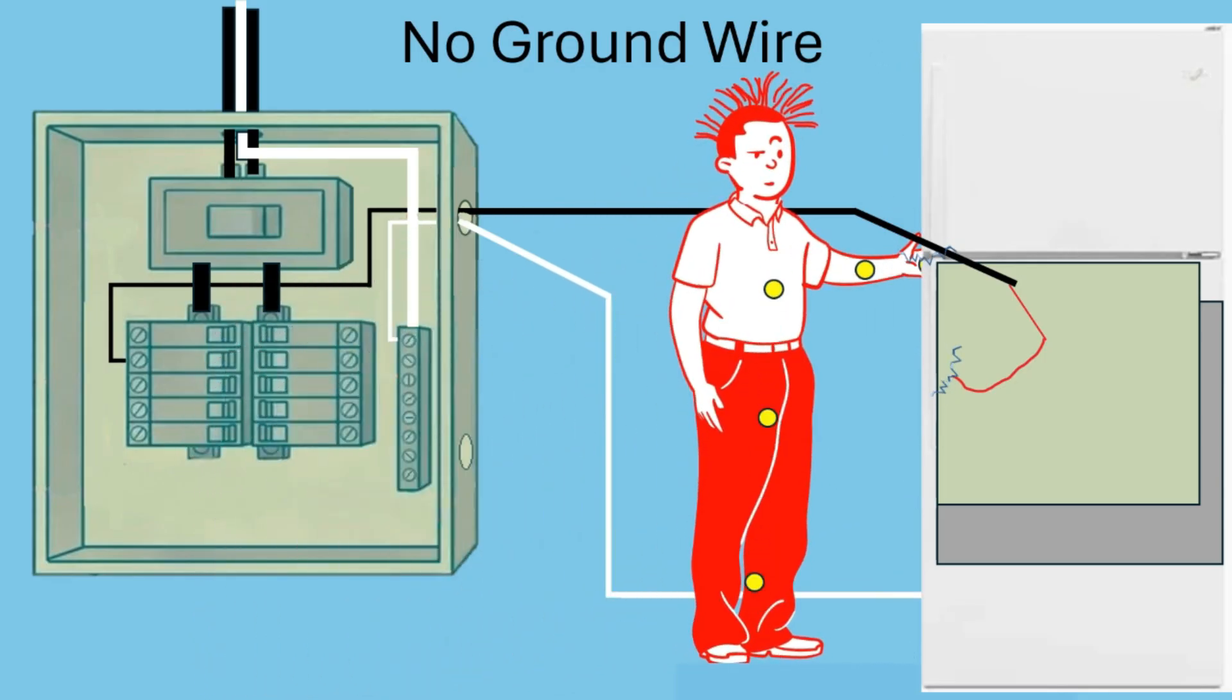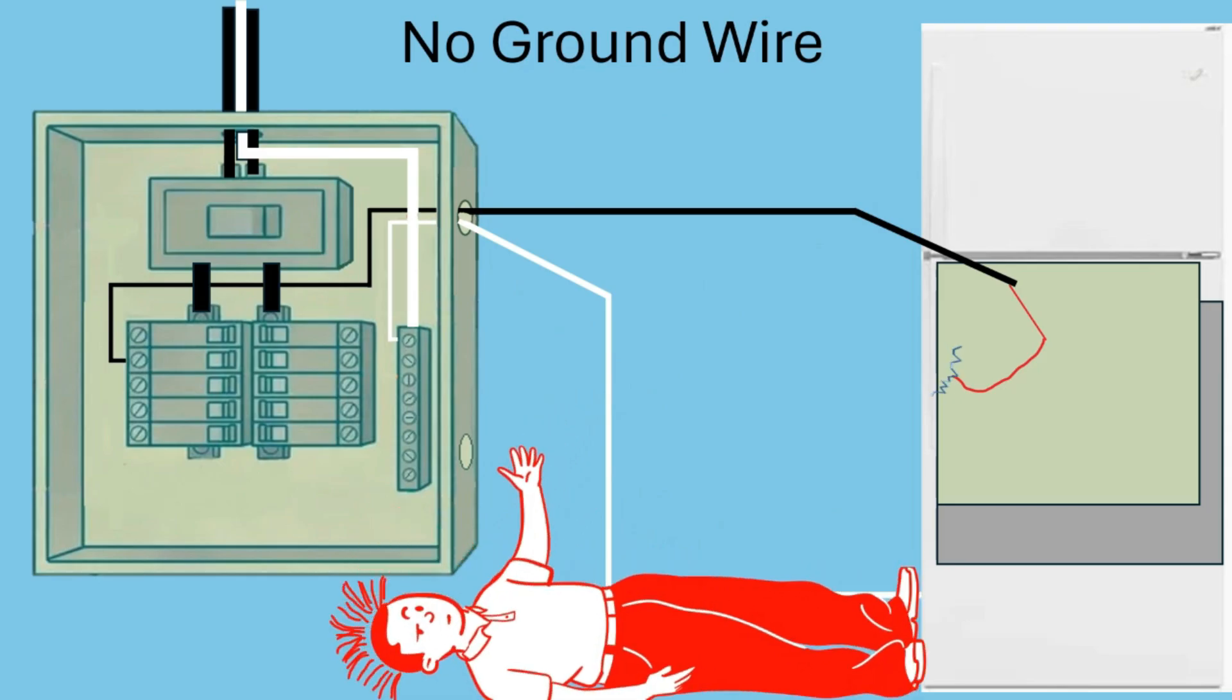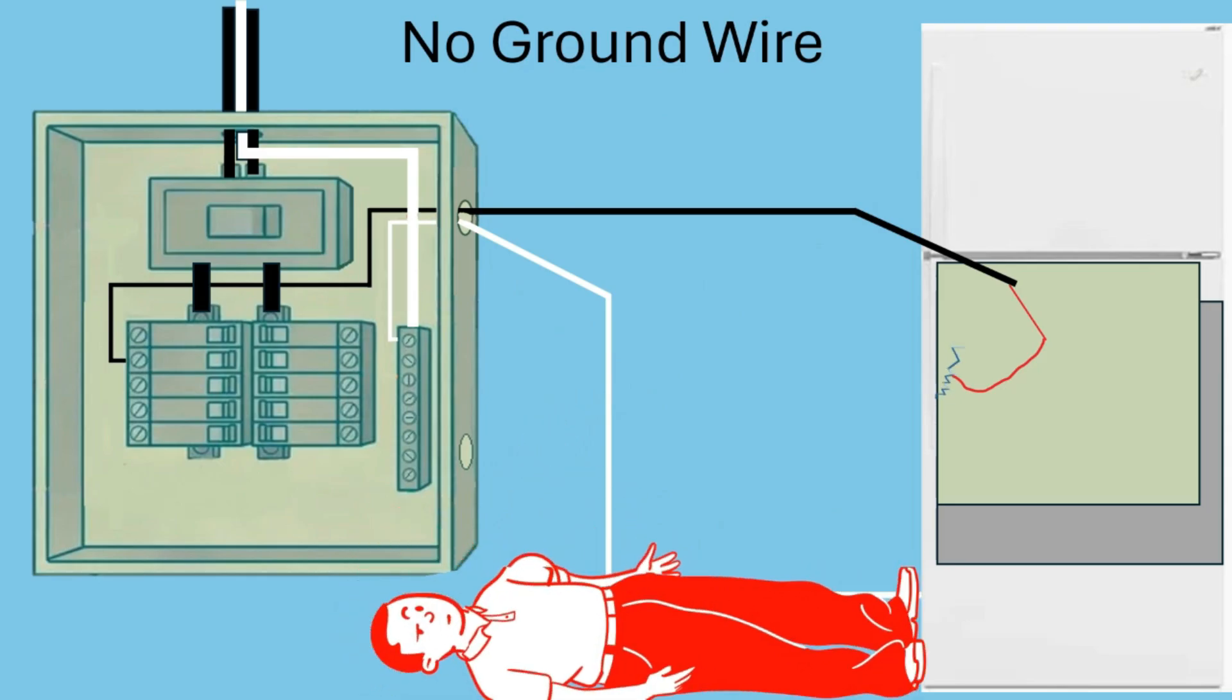Well that entire washing machine will now be energized and if somebody walks up to it and touches it to put a load of laundry in it they have the potential to be electrocuted. So when you have a grounded outlet basically you have a ground wire running from that washing machine back to the electric panel.